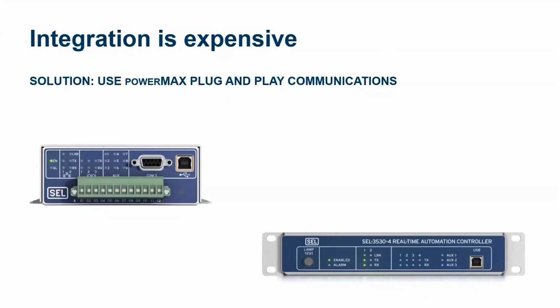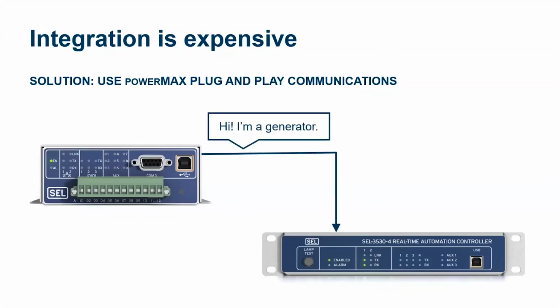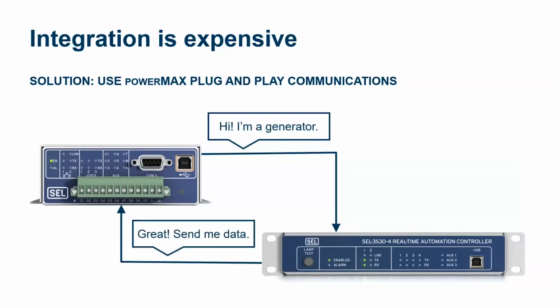Well, at SEL, we use plug-and-play communication between real-time automation controllers. Here shown is an RTAC communicating with an RTAC, publishing saying, hey, I'm a generator. And now the microgrid controller, the 3530-4, says, great, I'm a microgrid controller, so you generator, you start up and go to set point. So now what used to take days, I've experienced weeks and months of communication challenges, is milliseconds. That is a complexity reset. That is a cost saver. That gets you back on budget and helps your ROI.